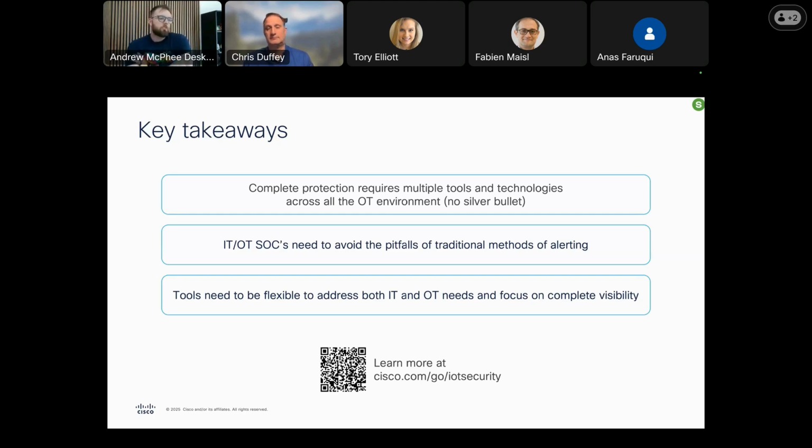So, how does Cyber Vision handle encrypted OT protocols? Cyber Vision doesn't decrypt the OT protocols. It'll see that they're happening. We'll see a relationship between two assets, we'll see the protocol being used, and we'll tell you it's encrypted. But we don't decrypt to do payload inspection of that, so we're limited in what we can see within the payload. Unfortunately, yeah. But it's really the abnormal situation that it's actually encrypted. Typically, it's in plain text and everything is plain.